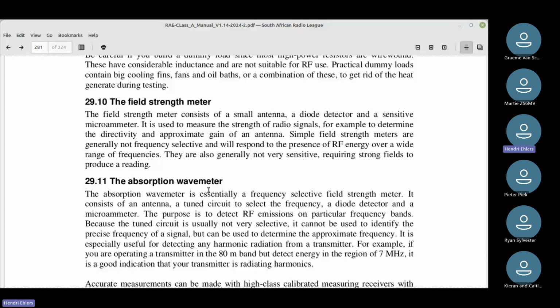Right, then we look at the absorption wave meter. The absorption wave meter is essentially a frequency selective field strength meter. So in other words, it's more accurate. You can actually see what frequency, or get close to the frequency. It works on the same principle, but it's got a tuning circuit so you can have the approximate frequency selected. But in today's terms they are also not very accurate. They are vague, and I guess it was the follow-up from the field strength meter, a major breakthrough. You can now adjust it.